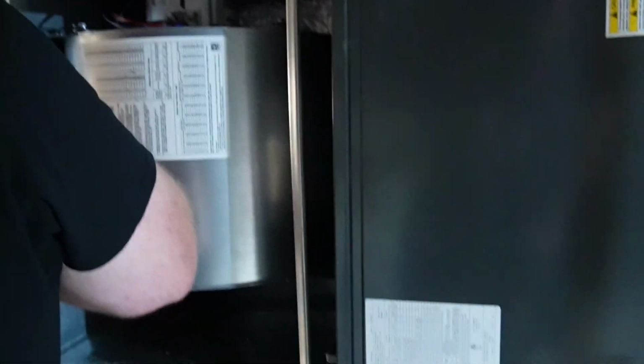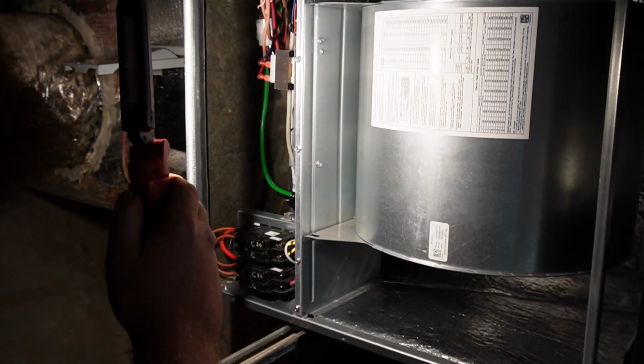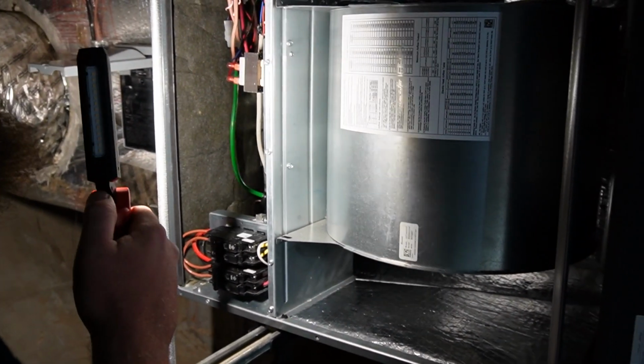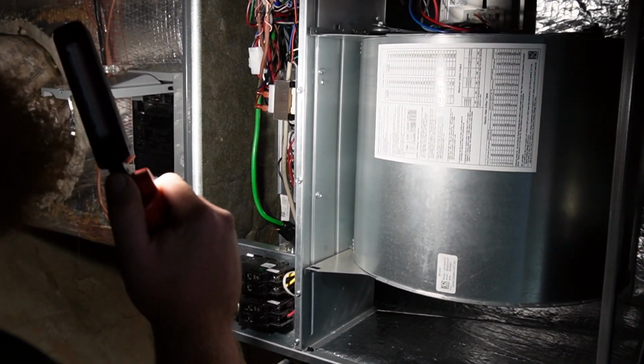So, yeah, we're going to check the outdoor too. We're going to offer to remove the old equipment. And we'll check, make sure the line set's the right size for this piece of equipment. Also want to check AHRI match-up, like I spoke about earlier, and see if this unit should be running with whatever's outside. We'll see what's outside.